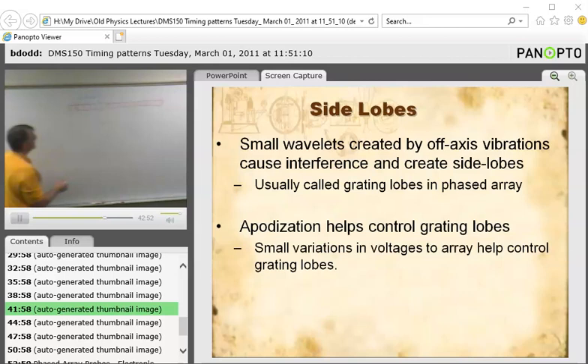So this piezoelectric crystal is going to expand a little bit, this one's going to expand a great amount, and these two next to it are going to expand somewhere in the middle, little baby bears. By changing this voltage here, we reduce our grating lobes. That's all it's doing, and it still gives us a nice big effective wave. And we call this apodization. So this variation in voltages that we're hitting our crystal with is called apodization. We're not hitting every single little crystallet with the same amount of energy. We're sometimes hitting it with less, and that reduces grating lobes.